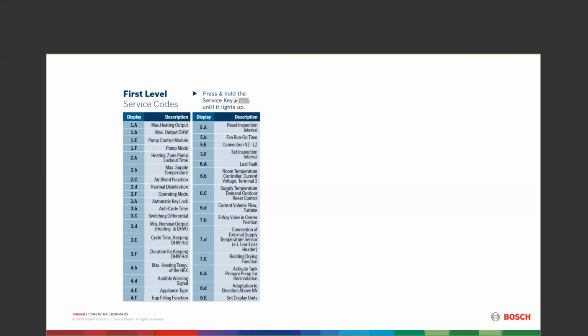So if I have a heating system where I only need, let's say, 50,000 BTUs, and it's a 100,000 BTU boiler, I can lock that thing down to 50% at 50,000 BTUs, and I'm locked in, good to go. Boiler's going to run nice and efficient. It's still got a turn down to its minimum. Great efficiency, great economy, and still allows for max output on your domestic hot water.